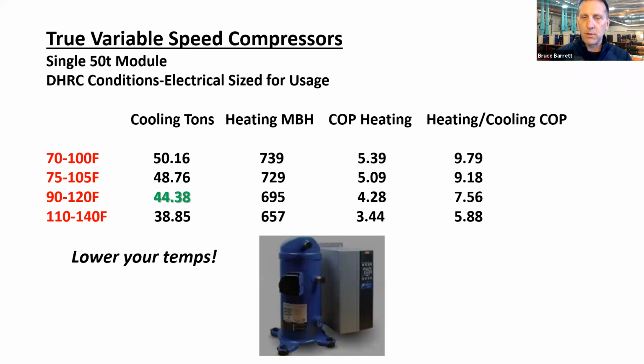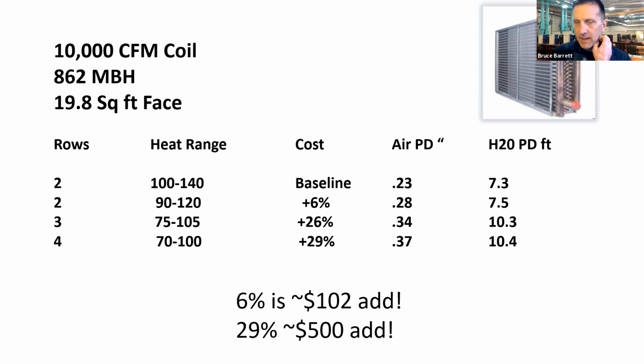With true variable speed, you get a small percentage improvement, not only at full load, but at part load conditions. Again, it's a PM motor, so it's going to have better motor performance out of the box. 7.56, making 120 degree hot water and about 44 tons. So I took it one step further in my analysis. I know a lot of people get nervous talking about lowering hot water temperatures and what that means for quality of comfort in the building. And I don't want to pick on Texas too much. They're in a heck of a mess right now, but they have operating temperatures on their coils 160, 170, 180.